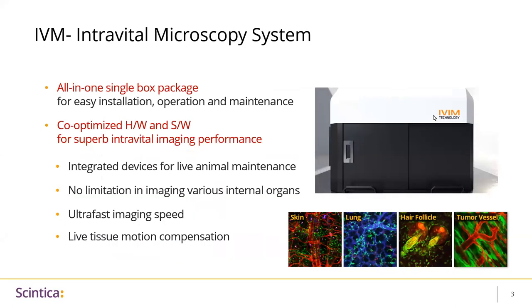IVIM Technologies has come up with a solution to make intravital microscopy easier and reproducible for non-experts as well as experts. This all-in-one single box package enables easy installation, operation, and maintenance, and it comes with hardware and software that are optimized for ultra-fast imaging, which offers no limitation in imaging various internal organs. This system is equipped with a live motion compensation function, helping acquire high quality images of moving organs, and it comes with specific hardware integrated in the system to maintain normal animal physiological conditions.